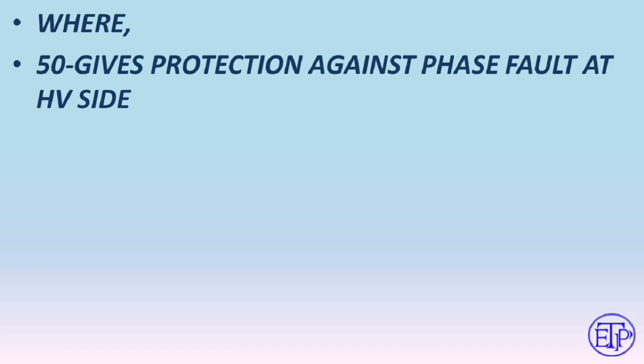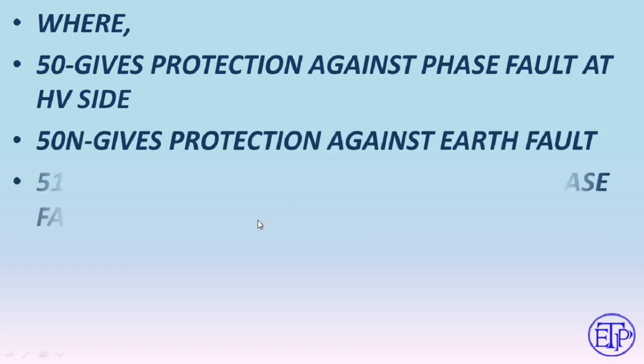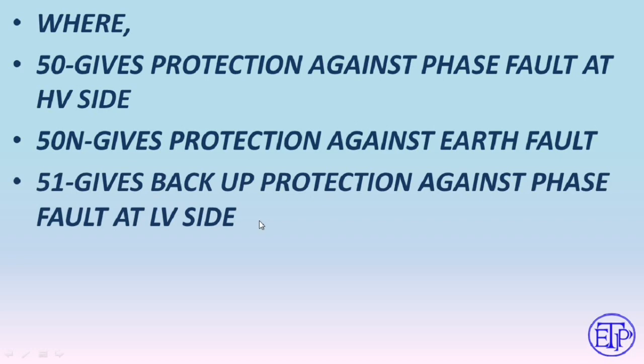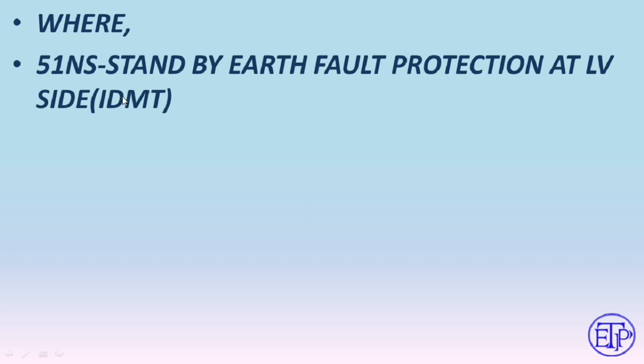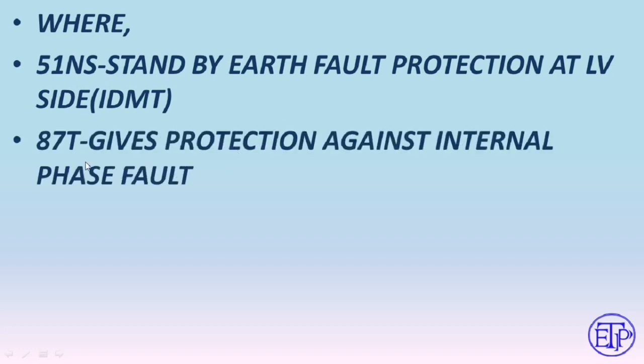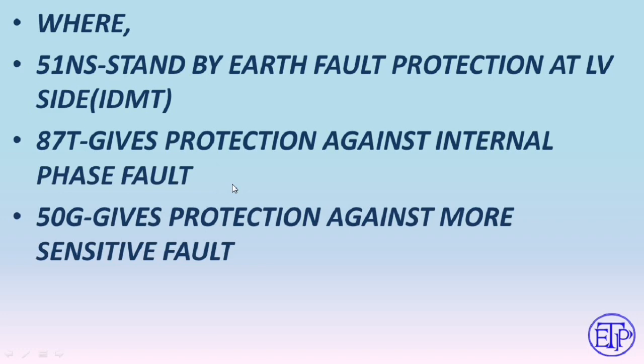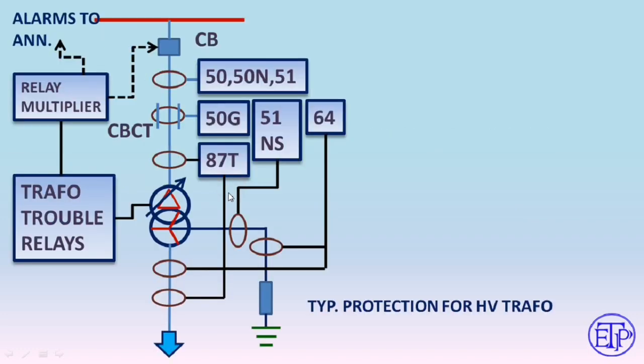Relay 50N gives protection against earth fault. Relay 51 acts as backup protection against phase fault at the LV side. Relay 64 is restricted earth fault protection — the primary earth fault protection for the LV side and it is a fast-actuating device. Relay 51NS is an inverse time standby earth fault relay acting as backup for the restricted earth fault protection 64. Relay 87T gives protection against internal phase faults via differential protection. Relay 50G gives protection against more sensitive earth faults.